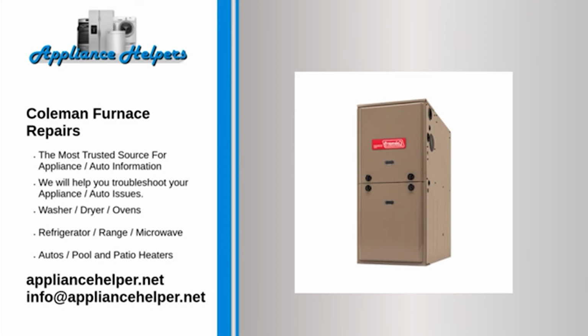Coleman furnace is not heating. The igniter gets very hot and glows bright orange to light the gas burner. If the igniter fails or cracks, the furnace won't heat. To determine if the igniter is faulty, remove the igniter and inspect it for cracks. If the igniter is cracked, replace it. If the igniter is not cracked, use a multimeter to test the igniter for continuity. If the igniter does not have continuity, replace it.